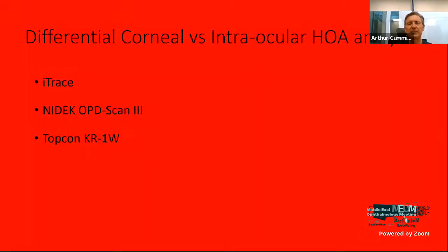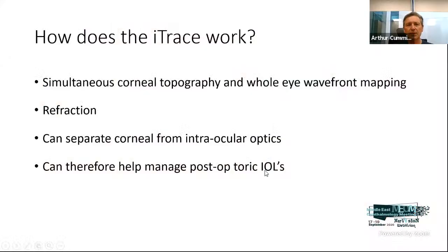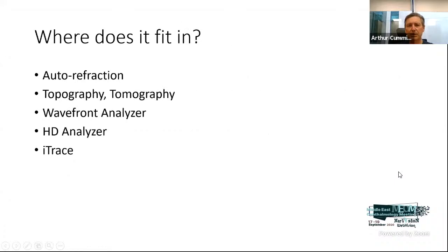Now, I spoke about this a little bit earlier today on these devices that have the ability to compare corneal versus intraocular wavefront. And iTrace I spoke a bit about. I'll share something more about that now. The NIDEK OPD-Scan does the same thing, as does the Topcon KR-1W. So how does it work? Well, it takes a simultaneous topography and a whole eye wavefront at the same time. It also does a refraction, has the ability to separate these images and really start understanding what's going on. And therefore, it can help us manage post-op IOLs, as we saw earlier.